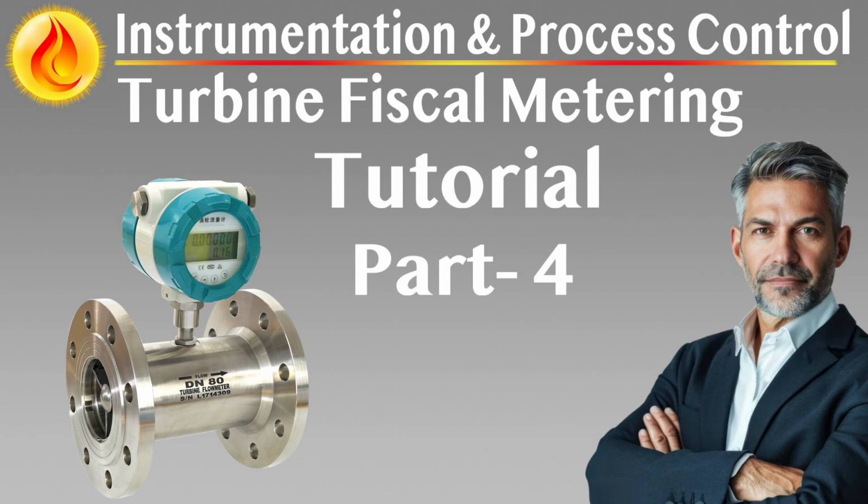Mass and volume computation system testing. Functional testing must verify that the control system correctly processes all measurement signals, converts them to digital values, and performs volume and mass flow calculations accurately. Simulated signals must be used to verify alarm thresholds, meter totalization, and data reporting.